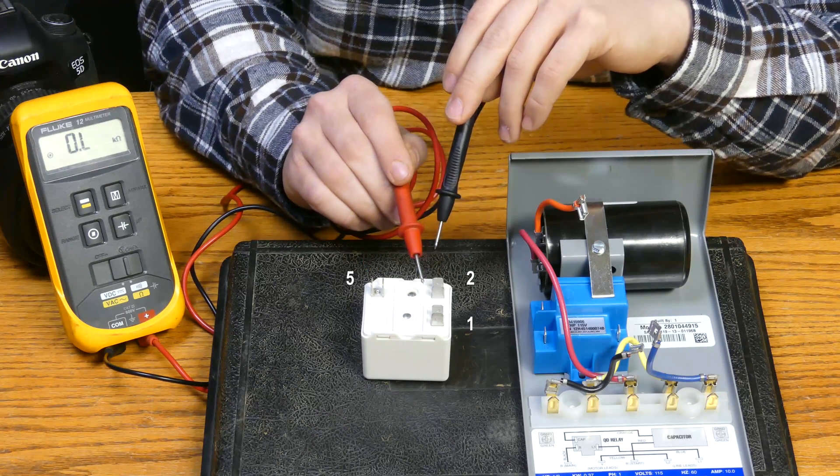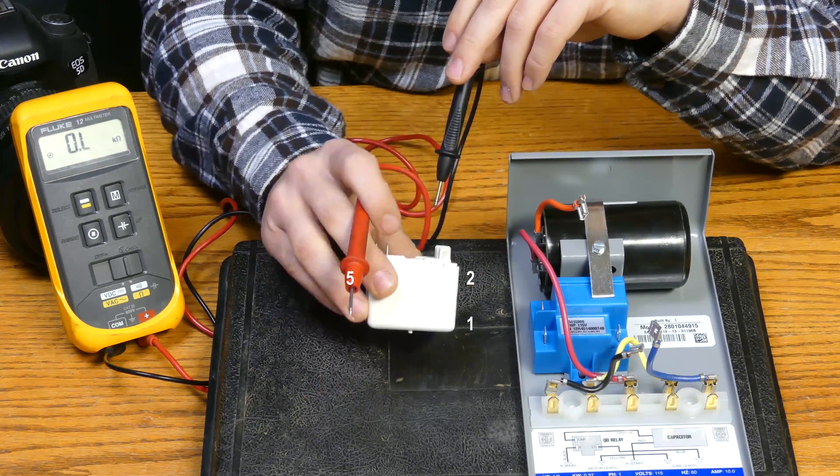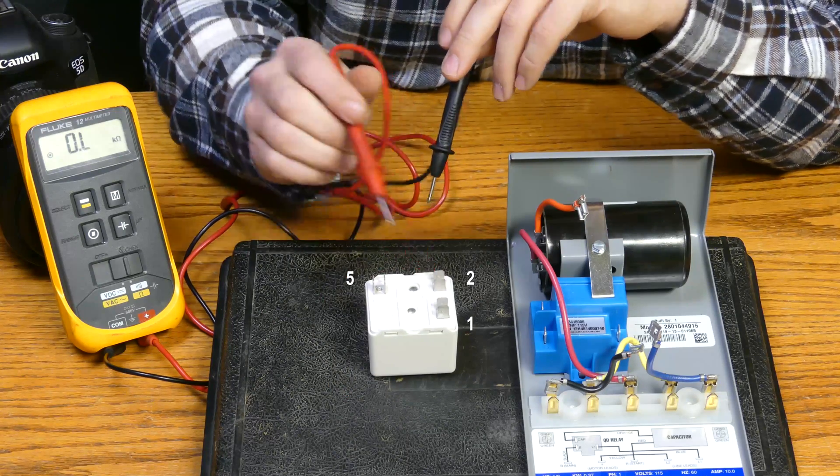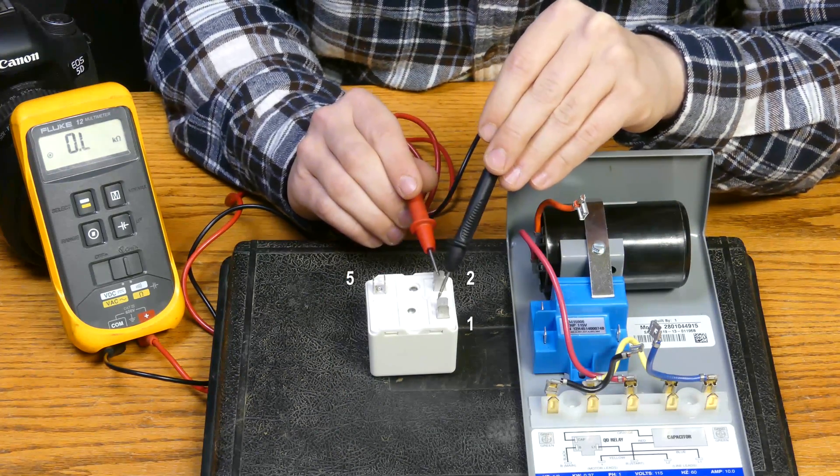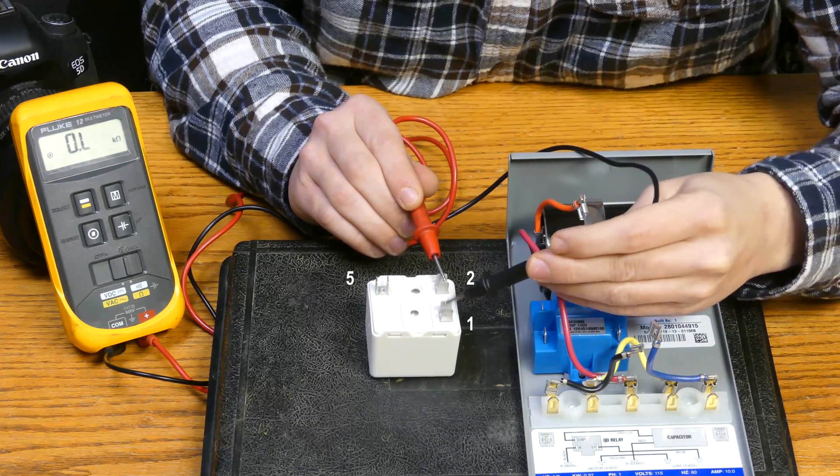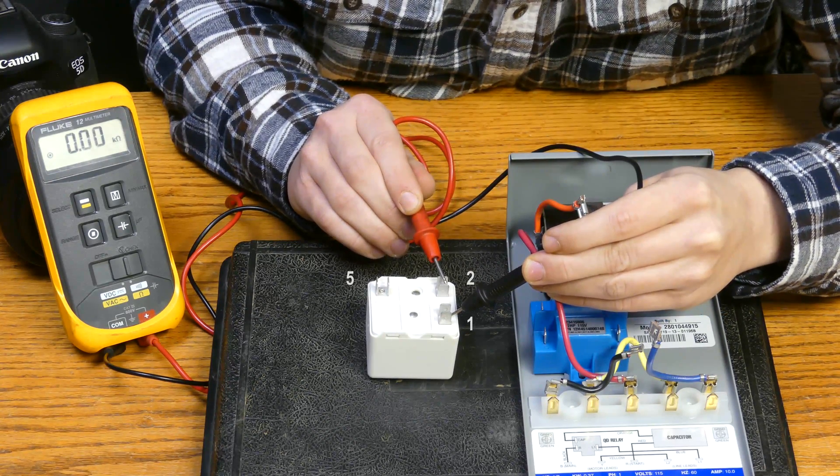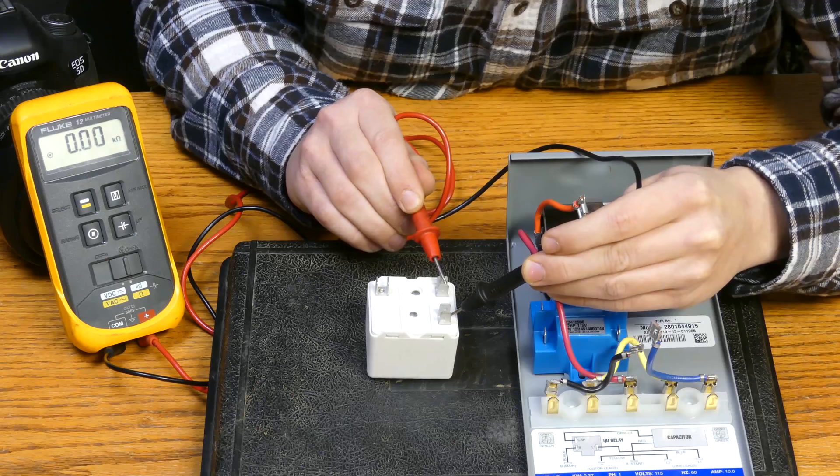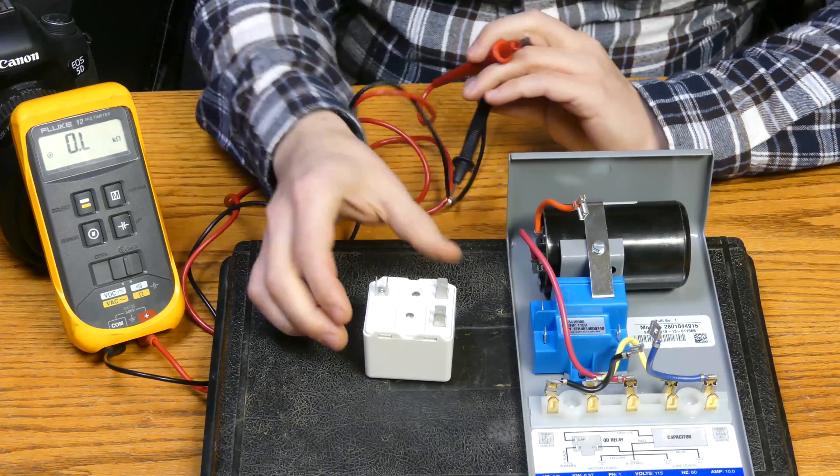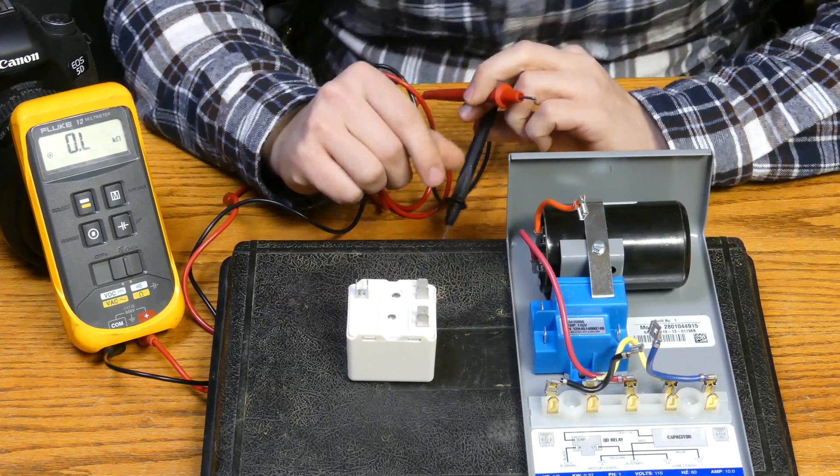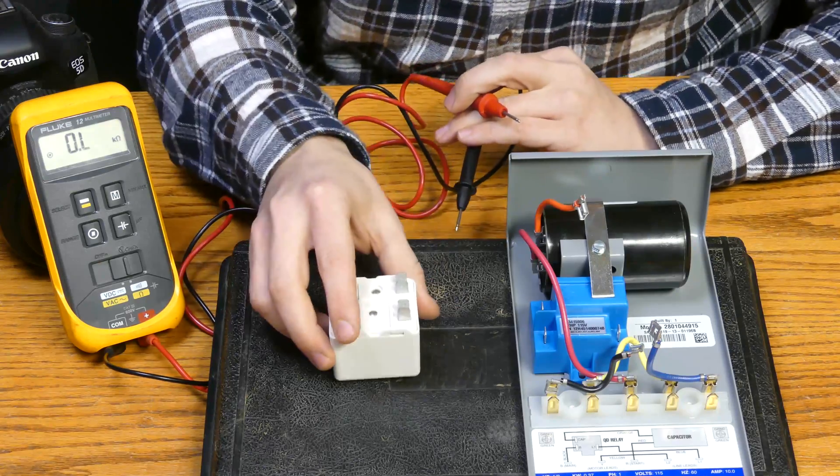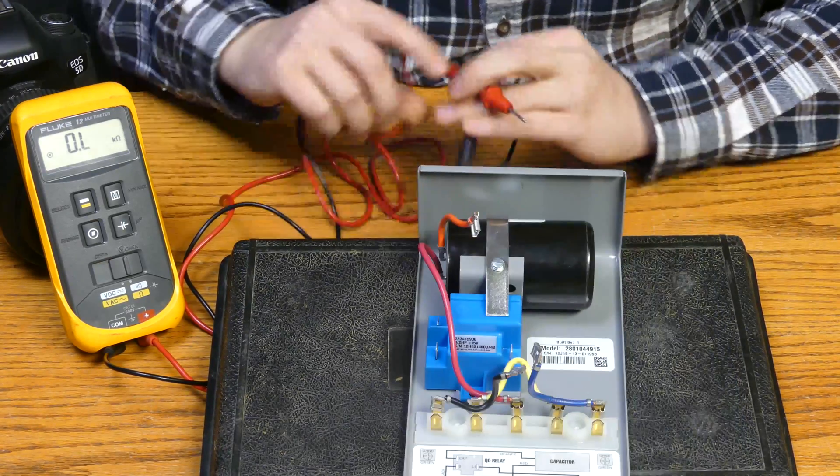Now the next one we're going to check is between 2 and 1, which is this one here. What we're looking for here is about 0. So let's get on there. So 0 it is. So we've successfully tested our relay. You may say well that's really easy, and that's because it is. So on to the next one here.